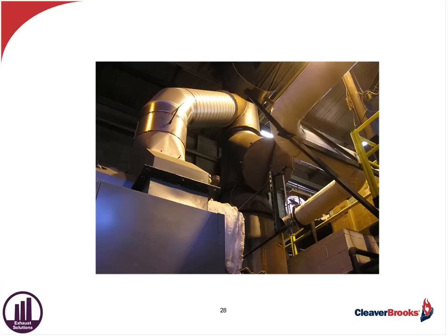And speaking about Y's, here's a good example. I'm coming out of this boiler and coming into the stack. But notice I don't bullhead into it. I don't just T into it. I use a Y to sweep the products of combustion into the stack. Try to impede the resistance to flow as much as I possibly can.